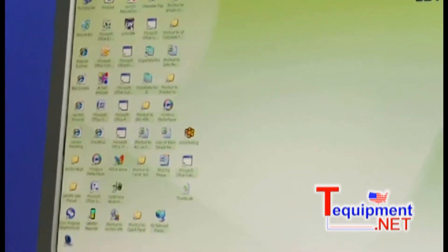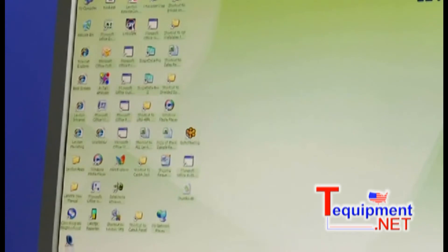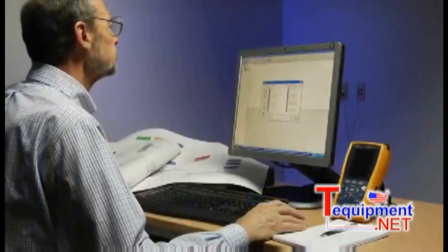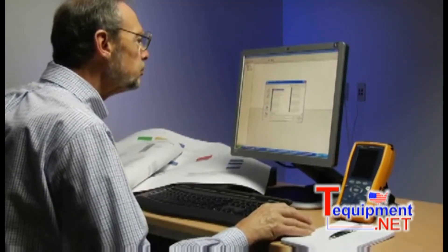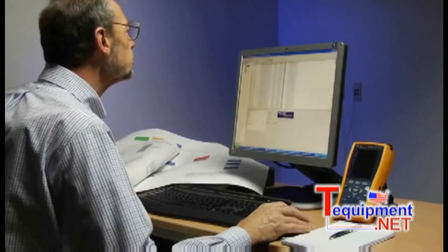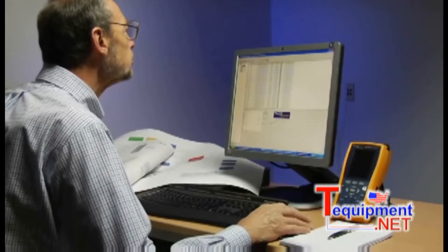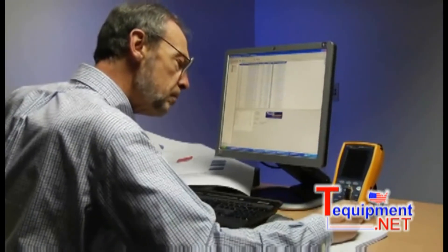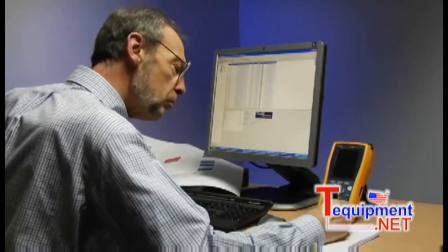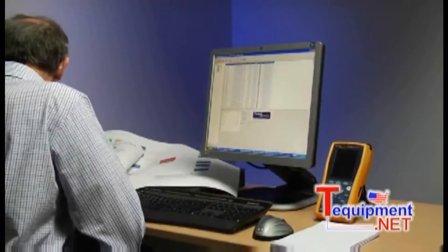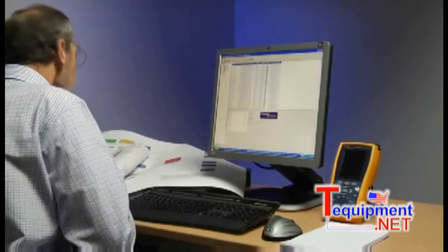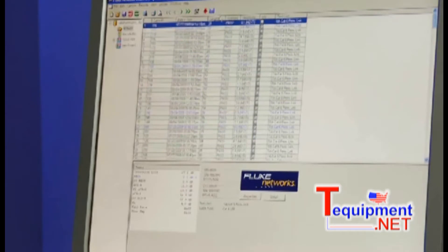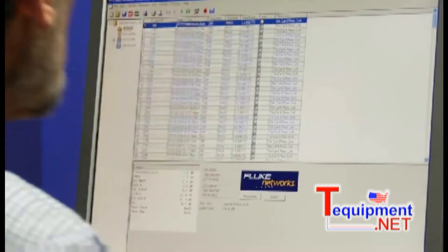The first step is to determine which links to analyze. It's not necessary — and would be extremely time consuming — to evaluate the influence of every link in the cabling installation on every other link. Instead, we'll follow a sampling plan to determine how many links should be tested. In this example, we're going to select five links for analysis. We'll call these the victim links. Here you can see that we've already loaded the in-channel test results and we're going to store the alien crosstalk files in the same job site folder.